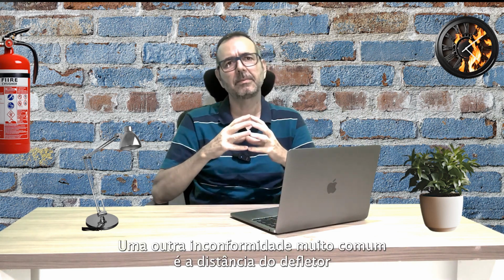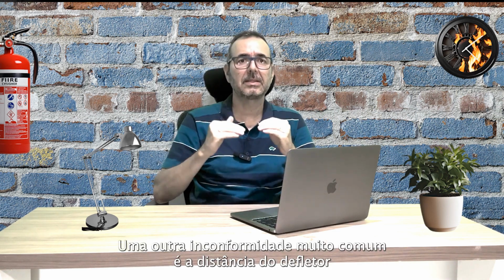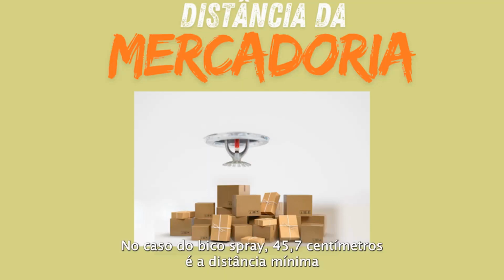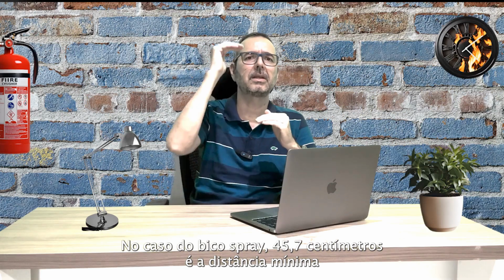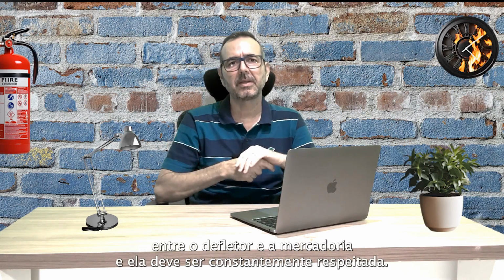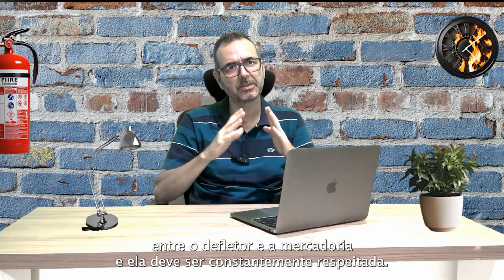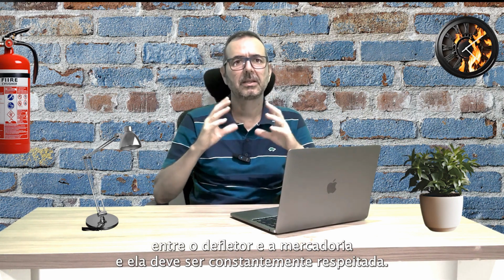Another very common non-conformity is the distance from the deflector to the merchandise. In the case of the spray nozzle, we have a distance of 45.7 centimeters. This is the minimum distance between the deflector and the merchandise, and it must be consistently respected. It is very common for us to have changes during the life of that building.